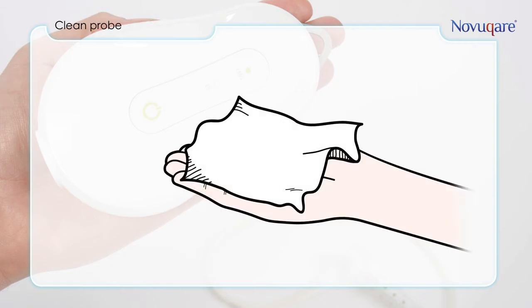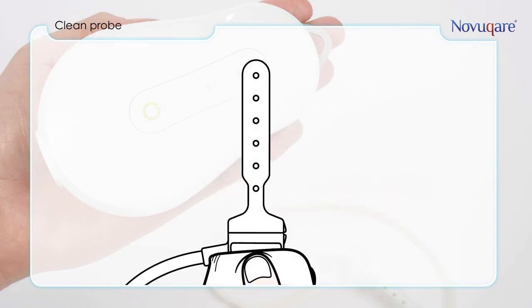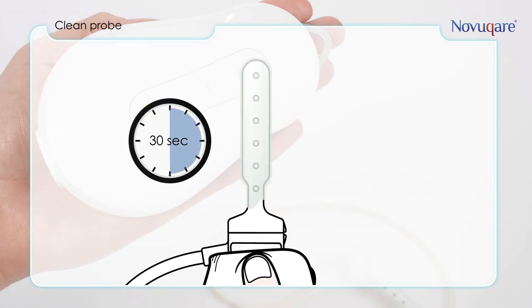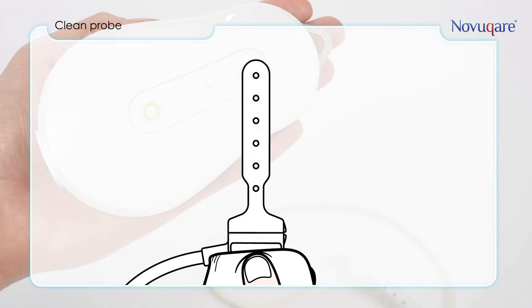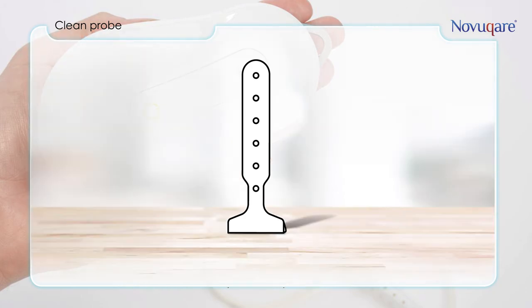Put alcohol 70% on a clean tissue in your ungloved hand and disinfect the probe for 30 seconds while constantly keeping the surface wet with alcohol. Remove the probe from the cable with the tissue while holding the cable with your gloved hand and put the probe in the cap of the probe container and let it dry.